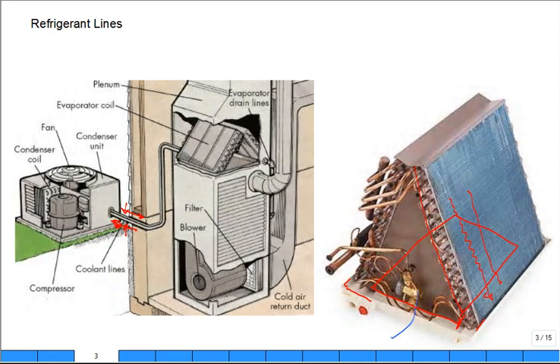It goes up and then across the coils like that. It's sealed up here so you prevent the air from bypassing it. The air needs to go across the coil to be cooled and when it does, if it's moist air, you get some condensate on that coil and it flows down, drains, collects in the pan and then comes off right here and it looks like they have two drain lines in place. One gets plugged and then you'll have an alarm for the second one and then make sure and get it serviced before you have overflow and spill.